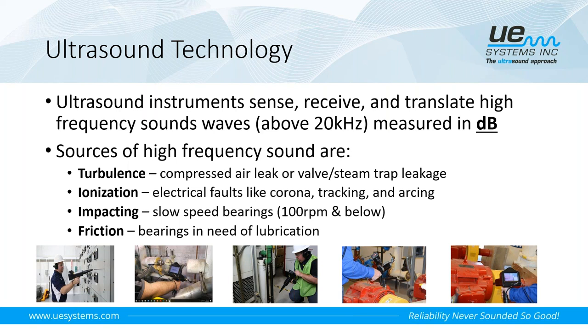Now, just like an infrared camera sees what you can't see, or an accelerometer feels what you can't feel, ultrasound hears what you can't hear. The instrument takes those high frequency sounds that we can't hear and translates them down into an audible range that we can hear in the headset as we're doing our inspection, or we get a visual readout on board the instrument in dB, or, if you're using an Ultraprobe 15,000, we can actually see the FFT or the time waveform right on the display of the instrument. So we can do some on-the-spot diagnostics on what's happening with that piece of equipment. And like I said before, we're measuring that sound in dB.